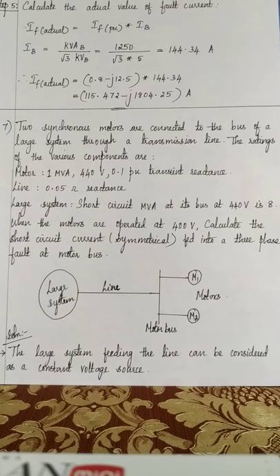with short circuit MVA at its bus at 440 volt is 8. That is, the MVA rating is 8, and the kV is 0.440. When the motors are operated at 400 volt, calculate the short circuit symmetrical current fed into a three-phase fault at the motor bus.